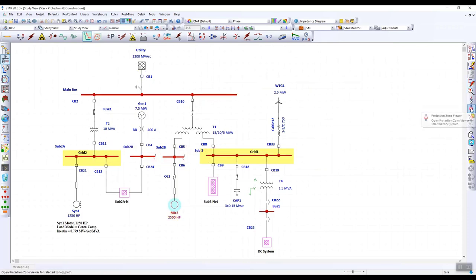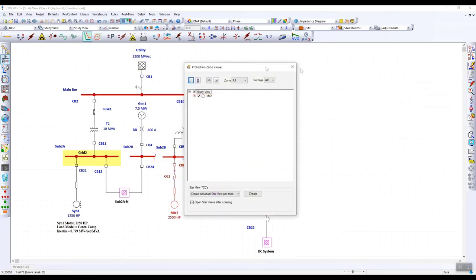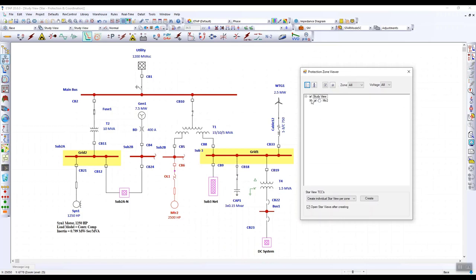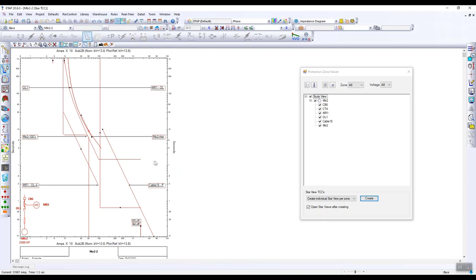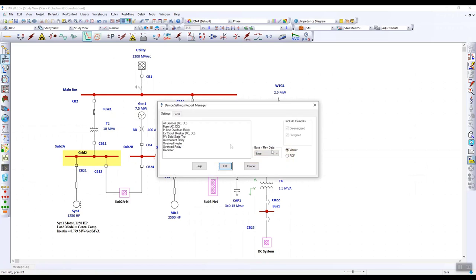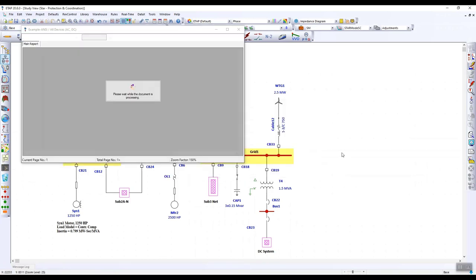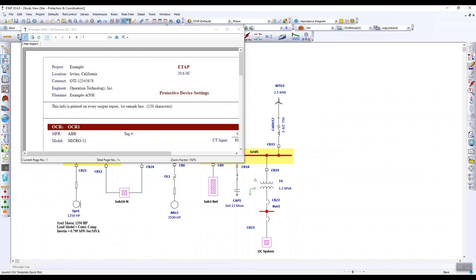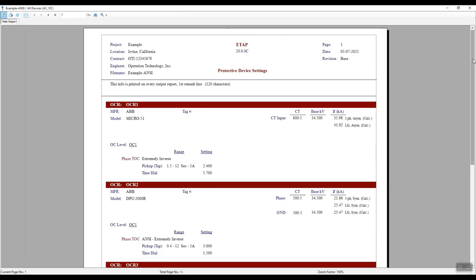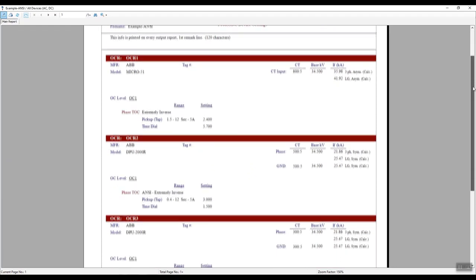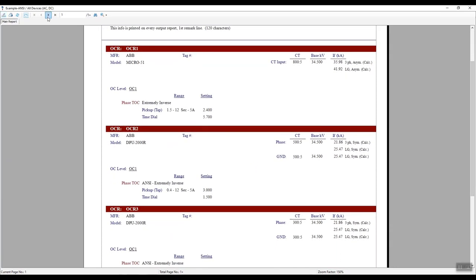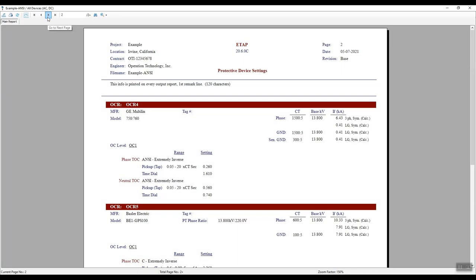We can use our protection zone viewer to see the zones of protection for this motor. From here, we can see the full list of all the devices connected to the motor, and then we can create a time current curve based on these devices. You can also create a device settings report for all the devices in your project. The device settings report will show all the settings for your protected devices, such as fuses, inline overload relays, low voltage circuit breakers, solid state trip devices, overcurrent relays, overload heaters, overload relays, and reclosers.